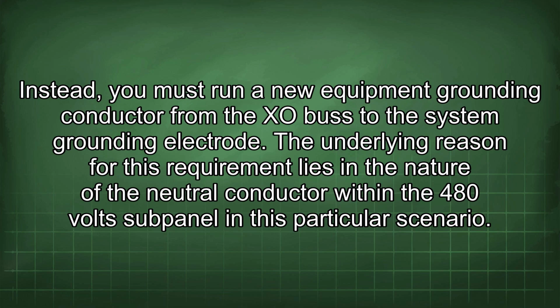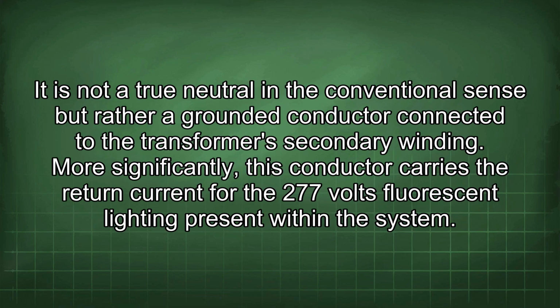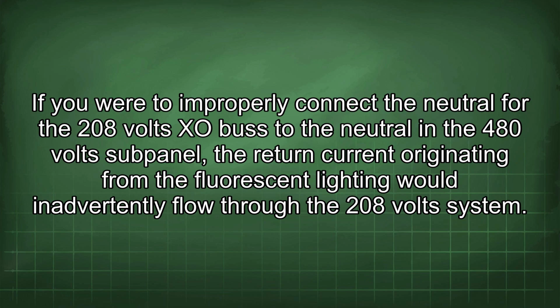The underlying reason for this requirement lies in the nature of the neutral conductor within the 480 volts subpanel in this particular scenario. It is not a true neutral in the conventional sense, but rather a grounded conductor connected to the transformer's secondary winding. More significantly, this conductor carries the return current for the 277 volts fluorescent lighting present within the system. If you were to improperly connect the neutral for the 208 volts XO bus to the neutral in the 480 volts subpanel, the return current originating from the fluorescent lighting would inadvertently flow through the 208 volts system.